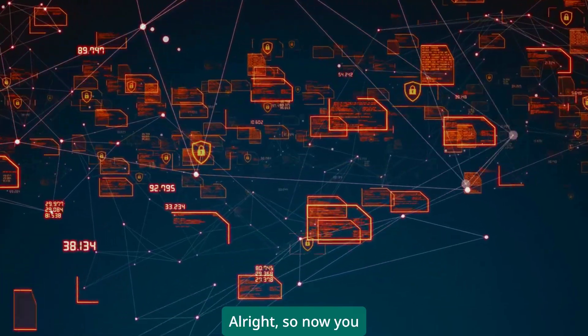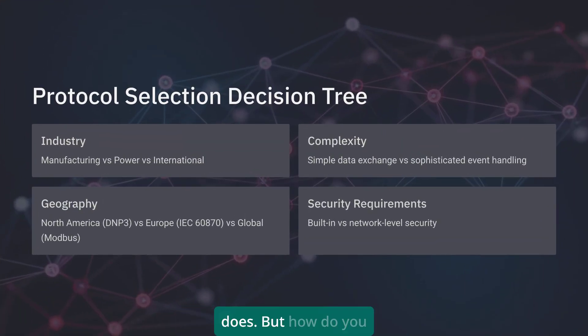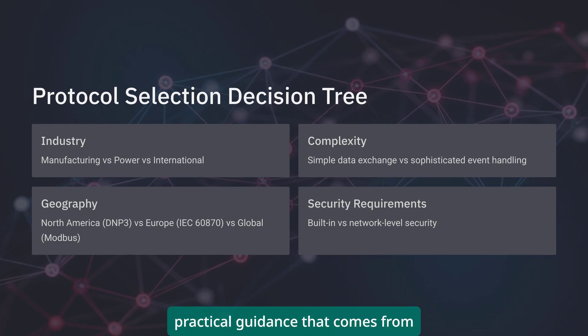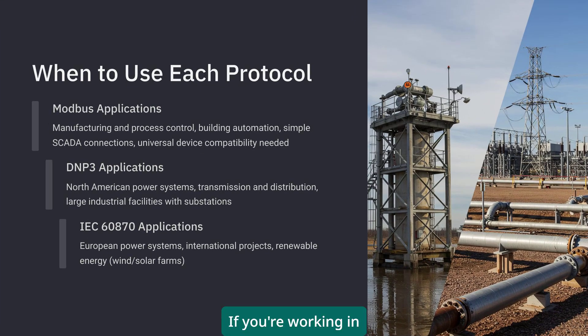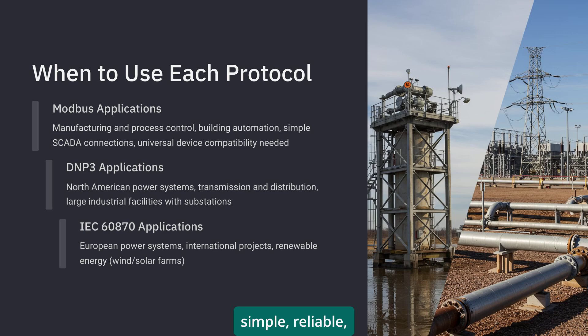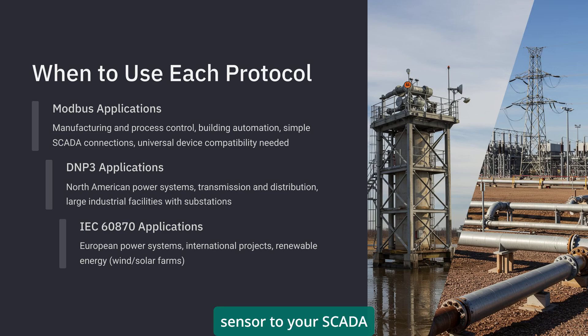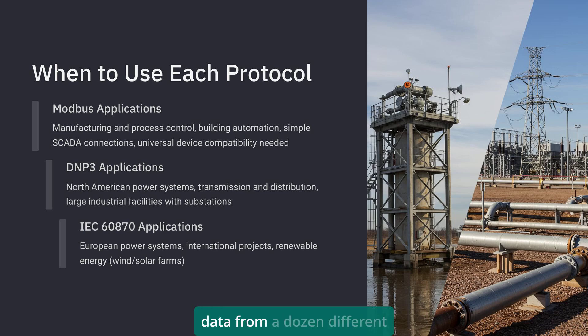All right, so now you understand what each protocol does — but how do you choose which one to use? Let me give you the practical guidance that comes from actually implementing these things. If you're working in manufacturing, process control, or building automation, Modbus is probably your best bet. It's simple, reliable, and everything speaks it. Need to connect a temperature sensor to your SCADA system? Modbus RTU over RS-485. Want to read data from a dozen different PLCs on your plant network? Modbus TCP will do the job beautifully.